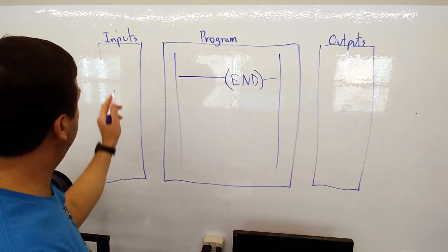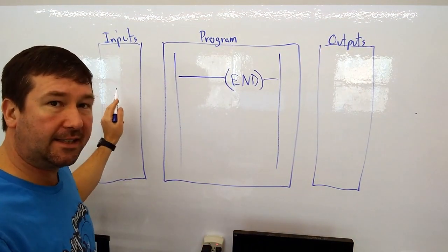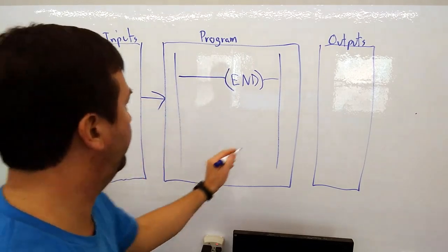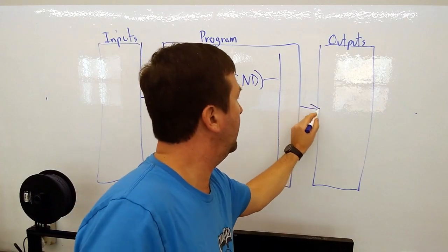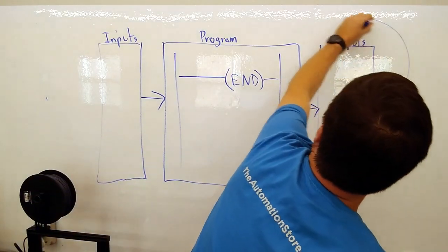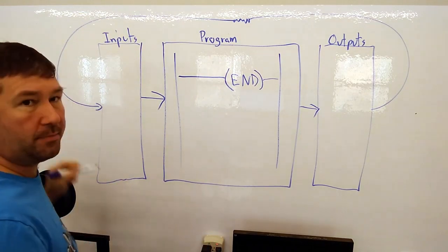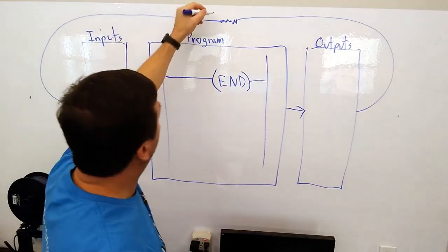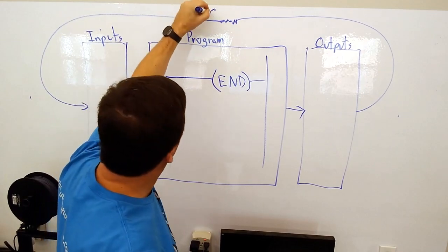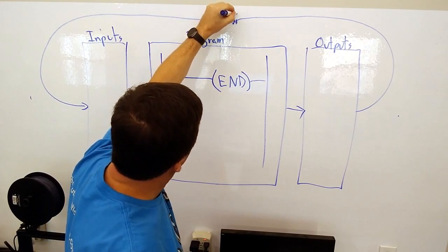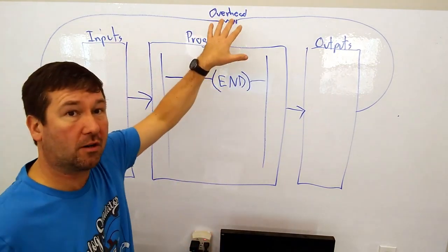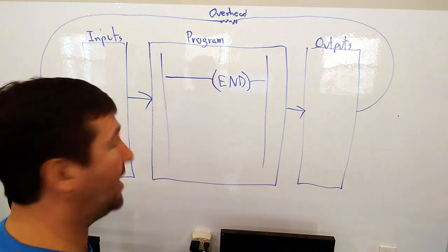And so the first thing a PLC does is it scans its inputs. Then it executes its program, then it updates its physical outputs, and finally it goes up here and it has a little something there, and then it goes back around to here. Now, we're not going to get into this little squiggly line up here, but it is called the overhead, and this is where the PLC does various maintenance steps. And actually, this is where it talks to RSLogix 500, some various things like that.